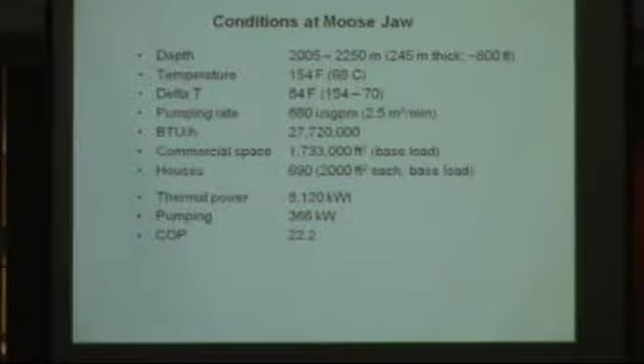The delta T tells us how many degrees Fahrenheit we're stripping out of the water. So in this case, the water would go into the exchanger at 154 degrees and come out at 70. So we've stripped out 84 degrees out of that stream of water running through the exchanger. Now we're producing this water at 660 gallons a minute, or about 2.5 cubic meters. This is quite a high volume. So you can imagine that volume of water with that delta T generates about 28 million BTU per hour. Well, that's just a big number.